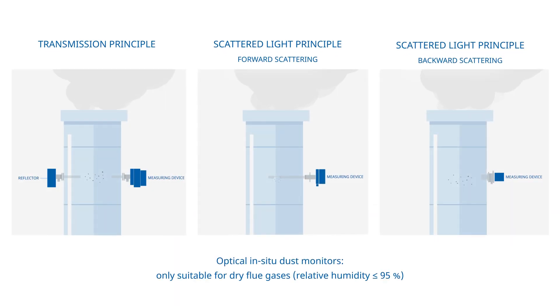Optical in-situ dust monitors are only suitable for dry flue gases with a relative humidity of less than 95%.